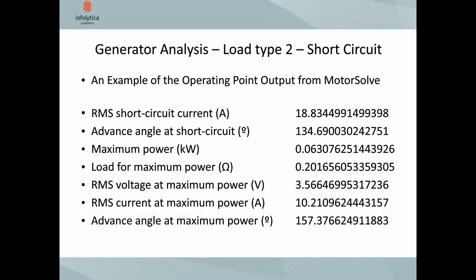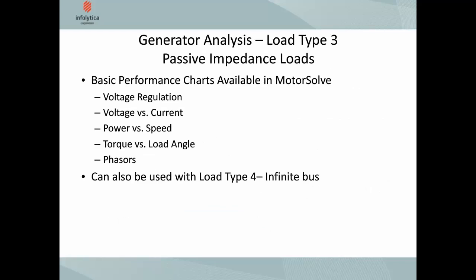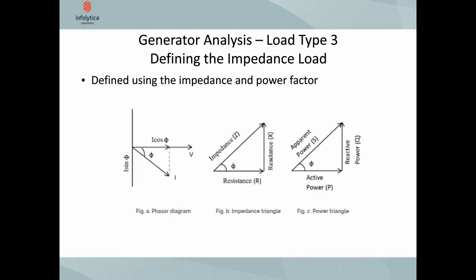A lot of loads will be of the passive impedance type — either purely resistive or reactive. Basic performance charts available in Motorsolve include voltage regulation, voltage versus current, power versus speed, torque versus load angle, and a phasor diagram. These charts can also be used for infinite bus type analysis. For the passive load, we use the impedance and power factor to define the load impedance.